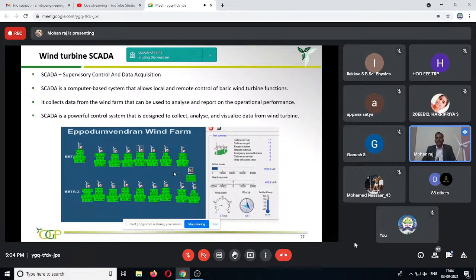I think you studied about SCADA. The expansion of SCADA is supervisory control and data acquisition system. So we can control the wind turbine by using SCADA, and also acquire data from the wind turbine. Normally SCADA is a computer-based system that allows local and remote control of basic wind turbine functions. We have the SCADA system in our company for 300 megawatt of wind turbines. We have a 24/7 monitoring station in the Chennai head office, so we can easily control the wind turbines. I can switch off the turbine and switch on the wind turbines from Chennai itself. I can also troubleshoot the wind turbine. What goes wrong in the wind turbine, we can see from the various parameters in Chennai itself. That is the purpose we use SCADA.